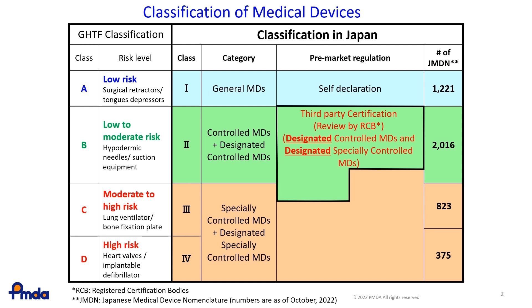without a review by the PMDA and approval by MHLW. Such third-party certification bodies are known as Registered Certification Bodies, RCBs.